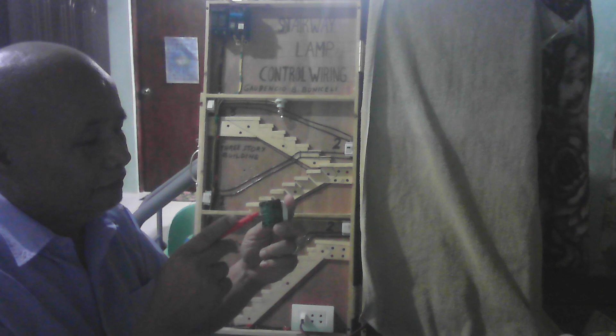The 3-way switch has 3 terminals. At the back there is a number: 1, 0, 1, 3. The 0 is for the common line, 1 and 3 are for the traveler. The numbers 1 and 3 you can interchange, no problem, but the common line should always be on the 0.